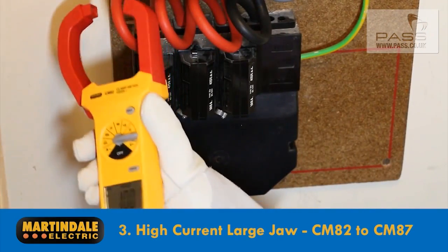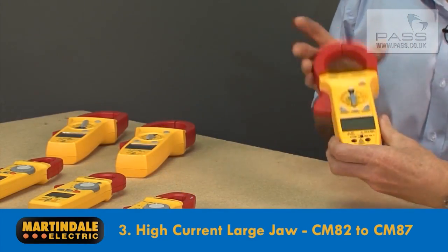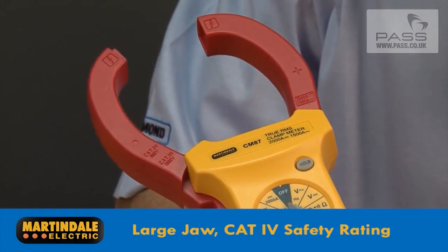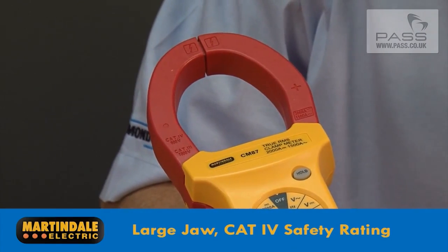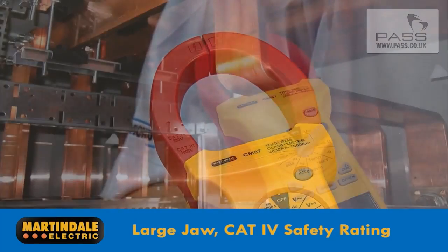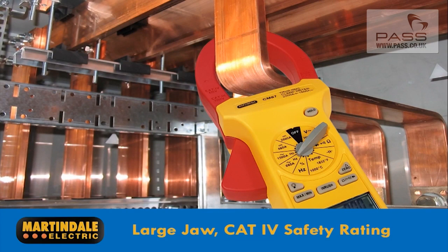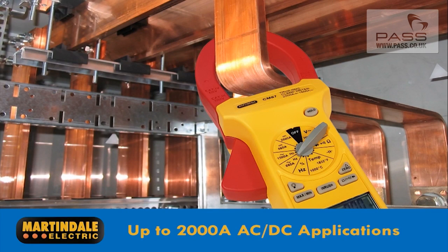For more specialist high current applications, there's the CM82 to CM87. These have large jaws with a Cat 4 safety rating for supply-side applications and are suitable for use on busbars in industrial and utility applications with current ranges up to 2000 amps for AC and DC applications.